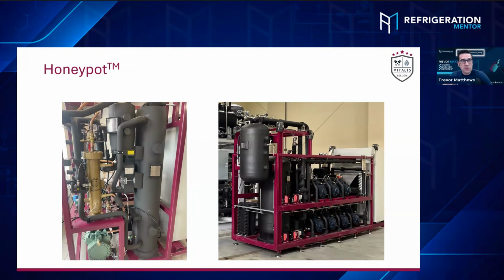Okay. So let's just go back to that. You're in a vacuum, it's pulling down. You'd actually take a hose, put it on one of the service ports of the oil reservoir, and then put it into the oil bucket, the oil can. We typically have two connections in these vessels, one at the top, one at the bottom. So you need to connect the vacuum pump somewhere, and that will be the top port because you don't want to pull the oil into the vacuum pump. So you would connect the vacuum pump on the top port and the oil hose at the bottom port, and then you just pull the oil out of that canister of oil.